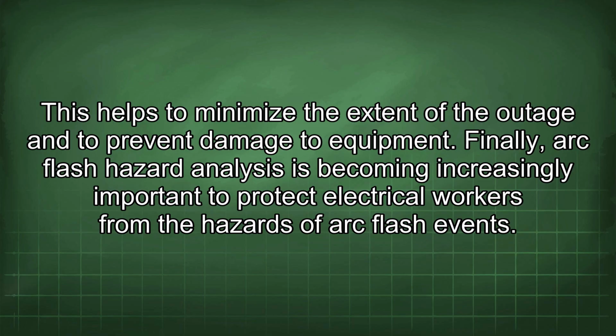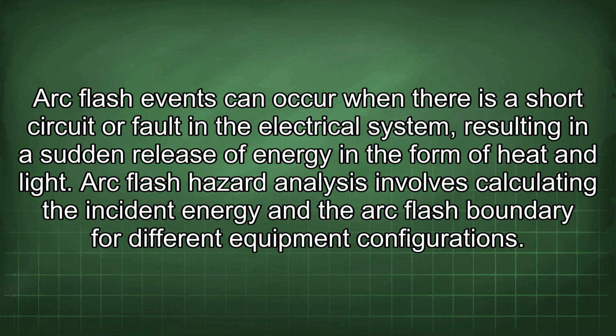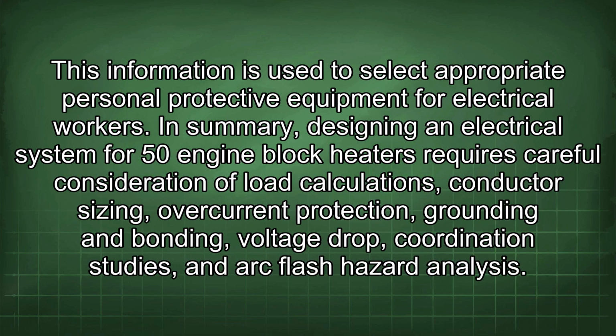Finally, arc flash hazard analysis is becoming increasingly important to protect electrical workers from the hazards of arc flash events. Arc flash events can occur when there is a short circuit or fault in the electrical system, resulting in a sudden release of energy in the form of heat and light. Arc flash hazard analysis involves calculating the incident energy and the arc flash boundary for different equipment configurations. This information is used to select appropriate personal protective equipment for electrical workers.